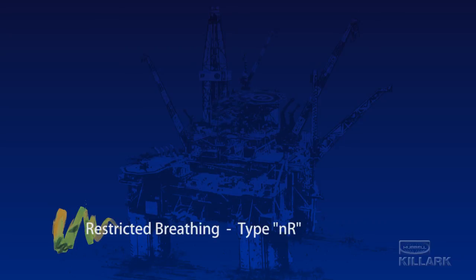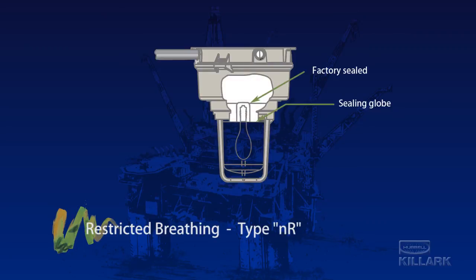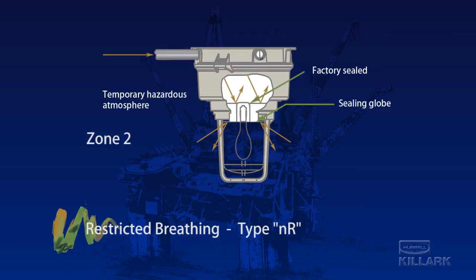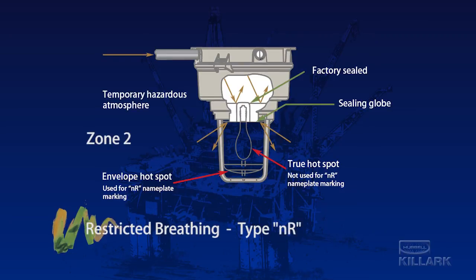Restricted breathing, designated NR, is a method of sealing and control for use in Zone 2 that has become particularly important in the design of lighting fixtures and other heat-producing devices. The extra measures used to prevent the entrance of gases and vapors from a short-duration flammable atmosphere that could occur in Zone 2 protect against developing explosive concentrations near elevated thermal points within the equipment. Testing for the temperature codes that will be assigned to the NR equipment can now be based on the cooler surfaces of the restricted breathing envelope.